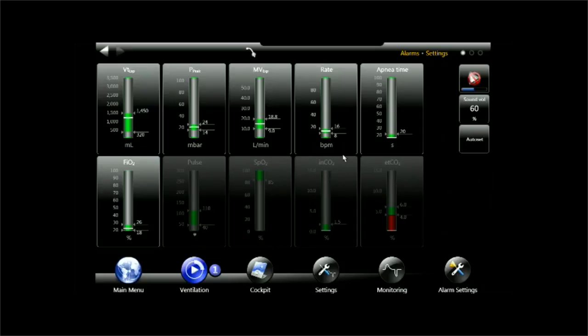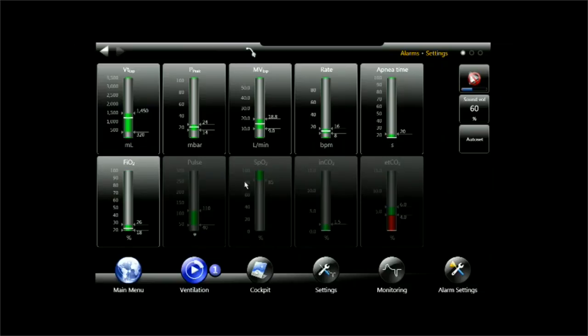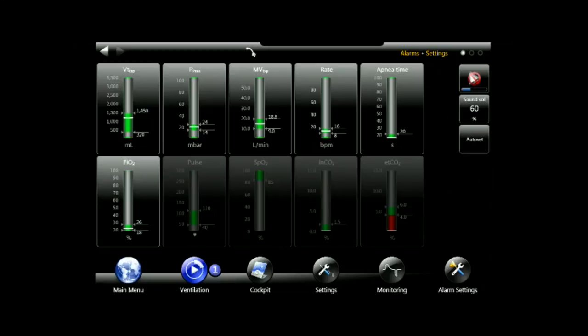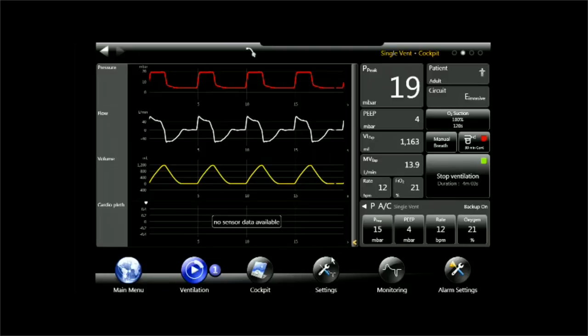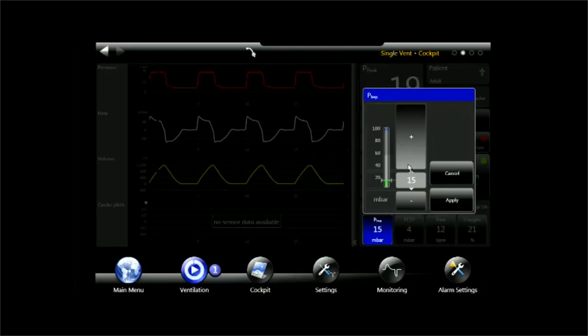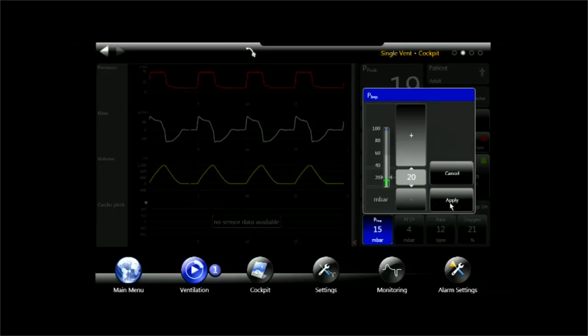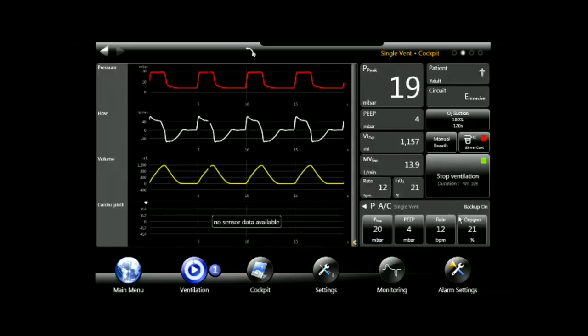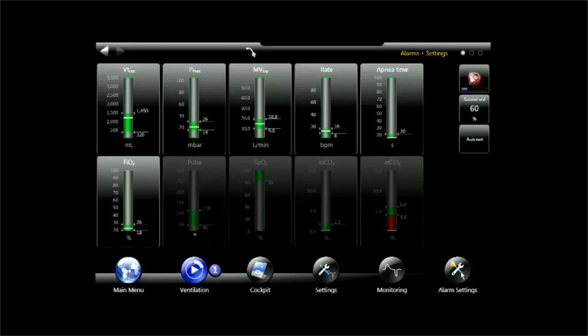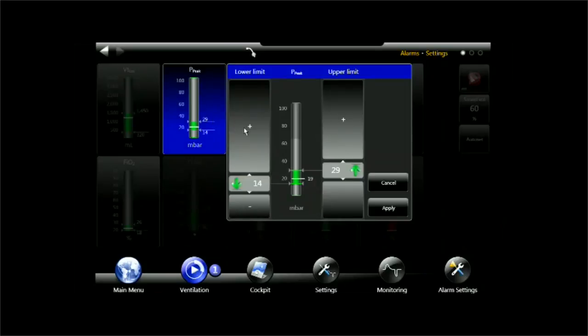There is a convenient function which helps me to avoid alarms. When I increase for instance inspiratory pressure, I go from 15 to 20, this automatically also increases my alarm setting. So this has now been increased to 29. So it's automatically been increased so we don't run into an alarm. This is a very user-friendly way, we call it AutoAdjust.